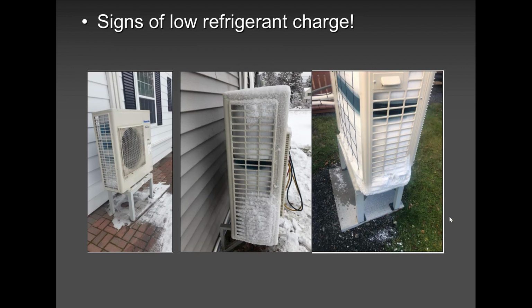Here are pictures, live pictures that came from customers that were showing F91. This picture is not that the unit did not go into defrost. The unit went into defrost, but the gas was not hot enough to melt all this. And the gas was not hot enough because there was not enough in the system. So please recover all the refrigerant, re-vacuum the system, and charge with new gas if there is no leak.